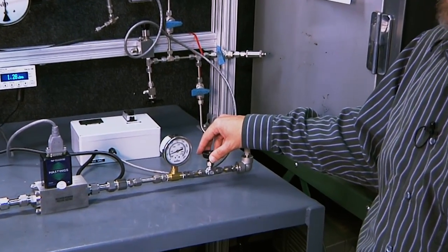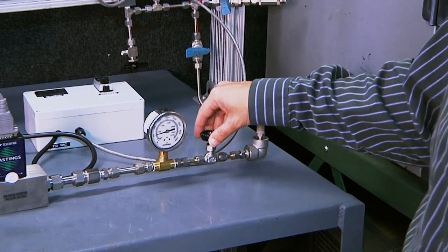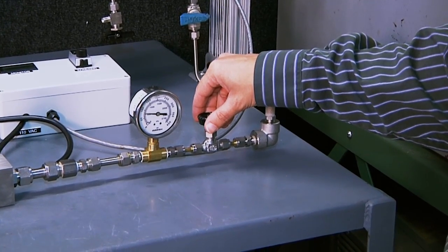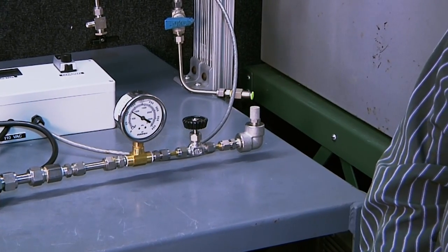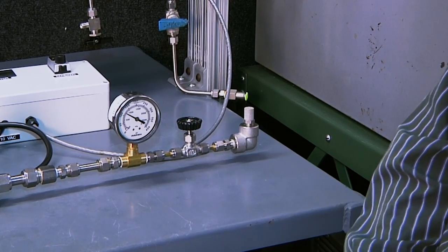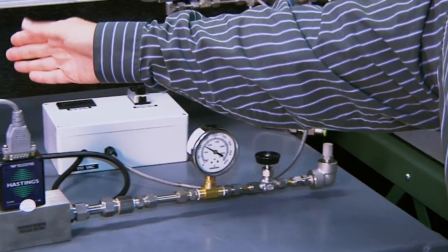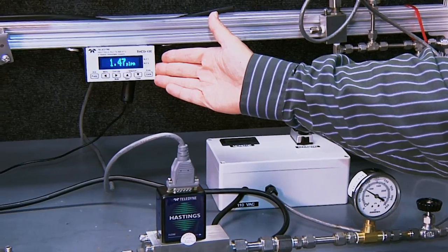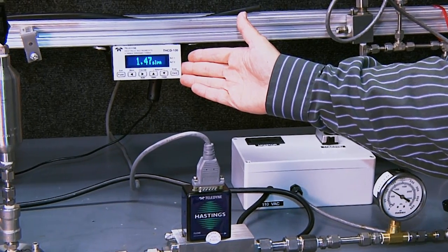If I slowly increase that restriction—now this could happen when lines plug up or things like that—we're going to run up. Now we've got something about 125 PSI of system restriction now. And if we come back over to our mass flow monitor, we'll see that we're still at about one and a half standard liters per minute.